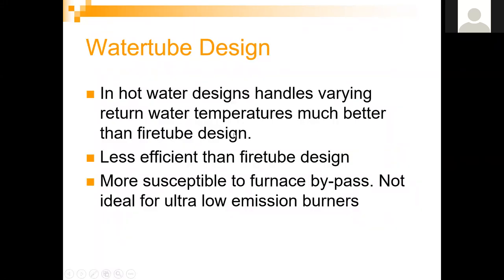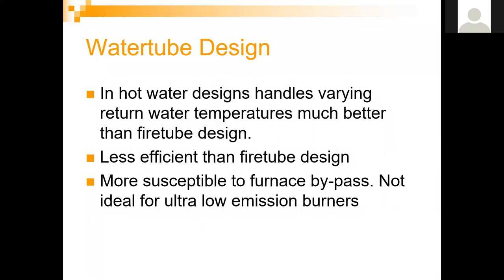Water tube design summary: in hot water designs, a water tube boiler — especially a flex tube like Bryan — handles varying return water temperatures much better than a fire tube. The serpentine tube design acts like an accordion that can flex back and forth with varying temperatures, which is why many were called flex tube boilers. It is typically less efficient than a fire tube design. Over time it can be more susceptible to furnace bypass, which isn't ideal for ultra-low emission burners, but it's a perfectly acceptable design as long as you maintain the integrity of the gas-tight seals.